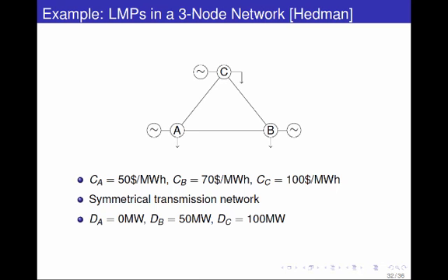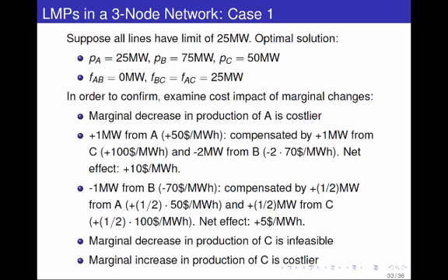Send from A to C. From A. It's the cheapest way to satisfy demand. So when you're shipping from A to C, how much? 1 megawatt. How much of that is going to flow over here? 2/3. And the rest, 1/3, is going to go the long way. And let's see if that causes a problem.